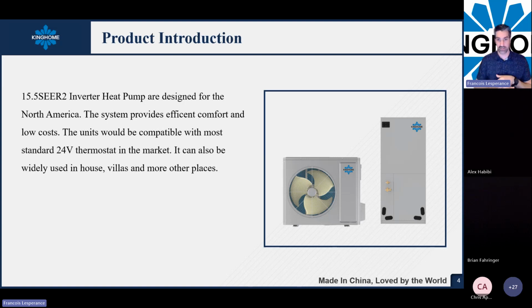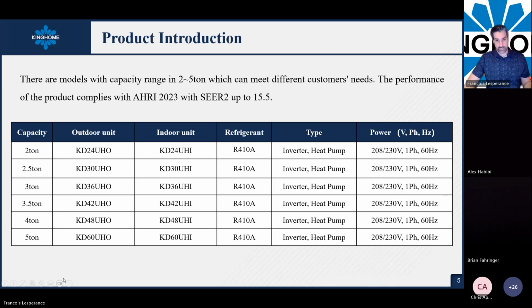Again, you will have a built-in 24-volt thermostat compatible connection, and you use some kind of air handler or A-coil to connect with your outdoor unit. For this kind of model, we have multiple cabinets, so you will have to match the right capacity. We have the 2 ton, 2.5 tons, 3, 3.5, 4, and 5. You will need to match your load calculation to the cabinet you want to use.